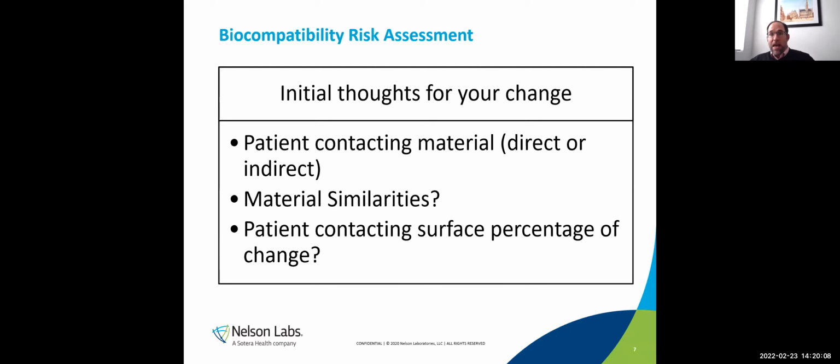So if you're evaluating different materials for a change, let's say you want more supply for your medical device, and so you want different suppliers for the same material, we can actually look at different suppliers and tell you based on some testing like FTIR or UV-Vis, some of these other ones, gravimetric even, how similar the materials are to one another.